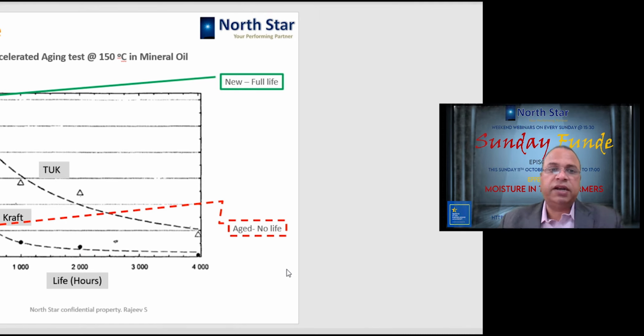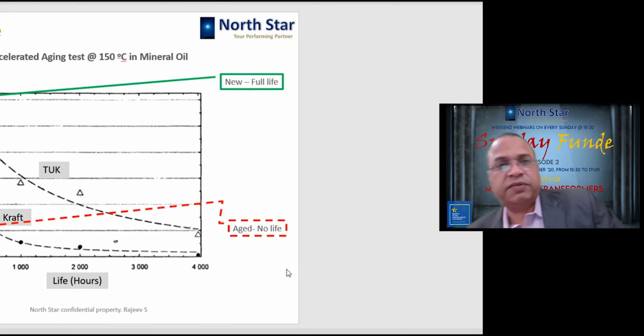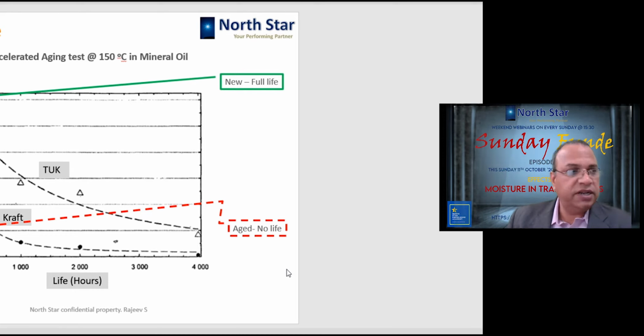So here we are trying to represent one again interesting concept of degree of polymerization. Here one graph is shown of an accelerated aging test done at 150 degrees, and the samples were kept in mineral oil. There were two samples, one is thermally upgraded kraft and second is normal kraft. TUK or thermally upgraded kraft is a special, superior insulation material which is chemically treated to make it capable of withstanding higher operating temperatures.